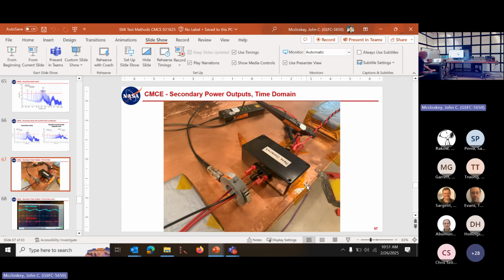So that really applies only to the primary power feed. So in this case, what's coming into the power converter on this side, this is your Gazinta. But common mode is something that we're concerned about on all cables. The common mode current is something that can radiate or cause crosstalk to neighboring cables, whatever. So any cable is a potential culprit for common mode.